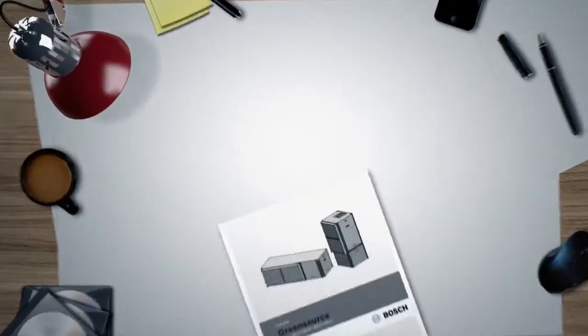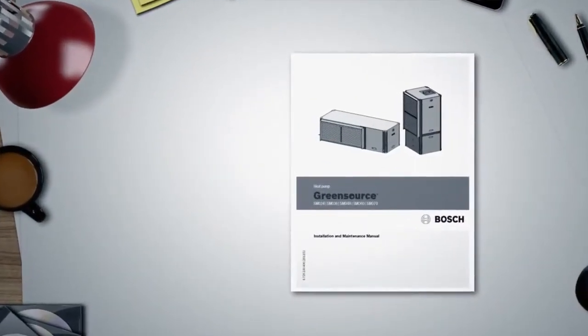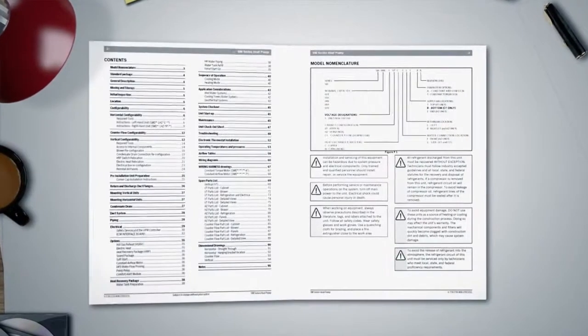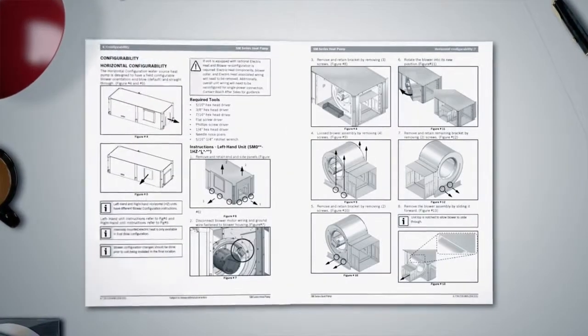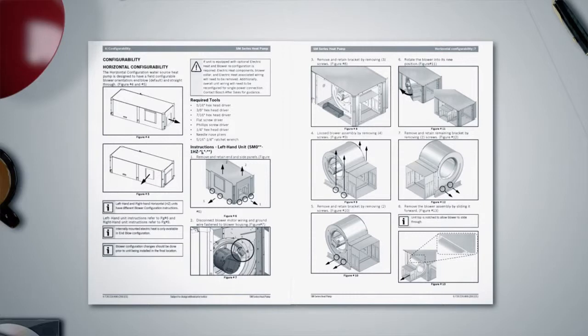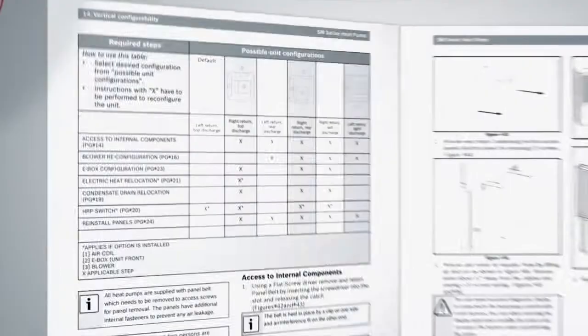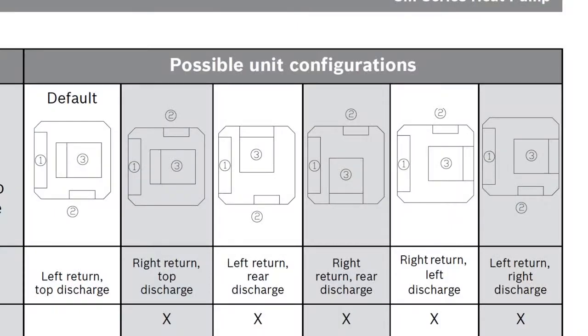Next, we will talk about field converting the unit. Instructions for field converting the horizontal unit supply air connections are illustrated in the Installation and Maintenance or I&M manual beginning on page 6. To convert the vertical unit, begin by checking the steps required using the table on page 14. At the top of the table are all the possible configurations for the vertical package. There are a total of 6.